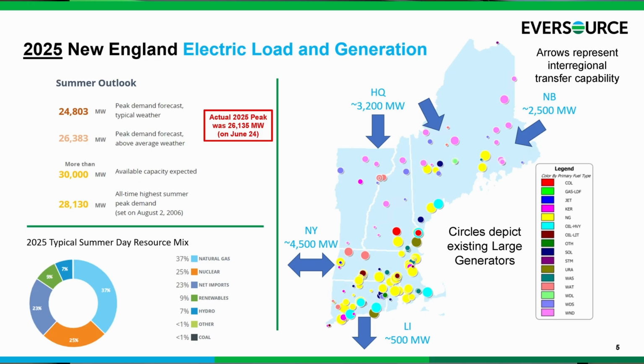Hydro-Quebec, I recently had to increase this number because the New England Clean Energy Connect project was brought online a few weeks ago. We can import approximately 3,200 megawatts from Hydro-Quebec. New York has several transmission lines along the western border. Remember, I'm aggregating them here, but we exchange power very frequently, and it goes back and forth in both directions to New York, approximately 4,500 megawatts. Then Long Island, we are normally exporting on the Cross Sound cable, which could be about 500 megawatts.